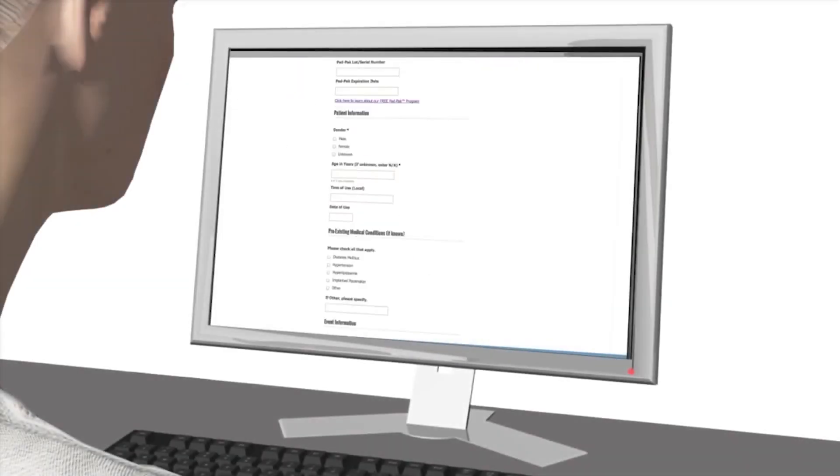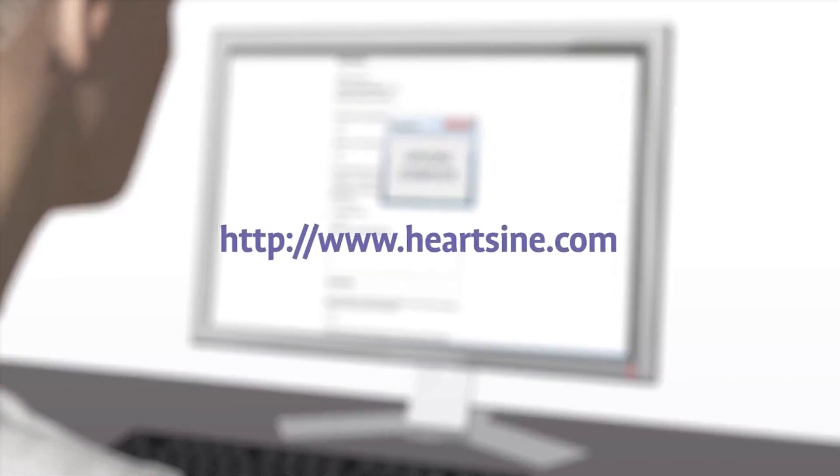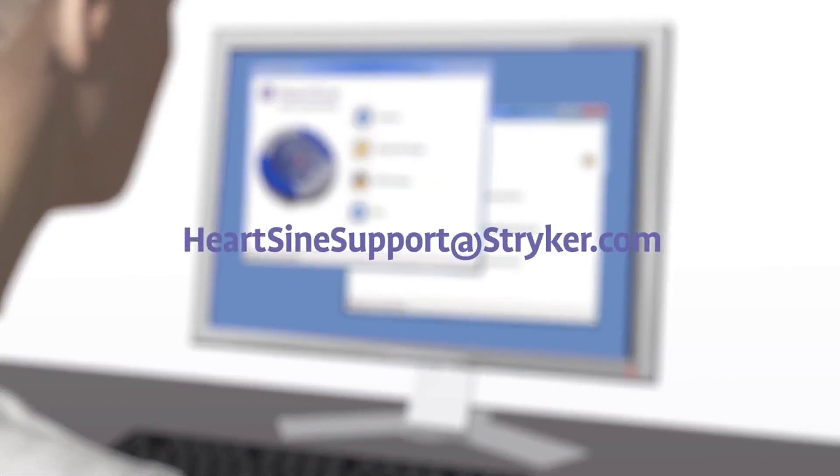After using the Samaritan PAD during a sudden cardiac arrest, submit the Saver EVO file and a completed customer event form to HeartSine — HeartSine will send you a free replacement pad pack. After downloading the event data, please erase the data from memory. If you need assistance to do this, contact HeartSine Technical Service.